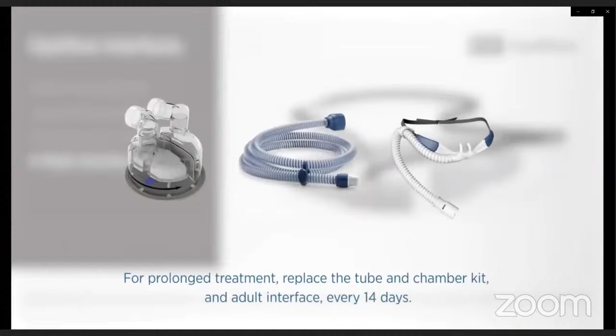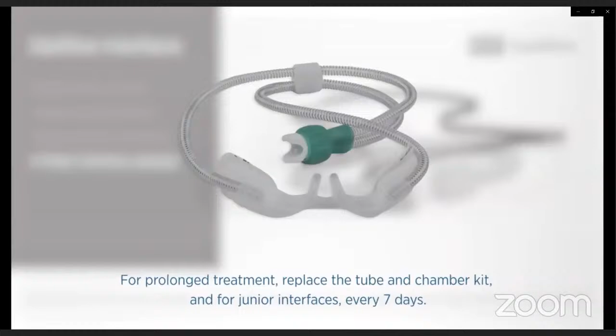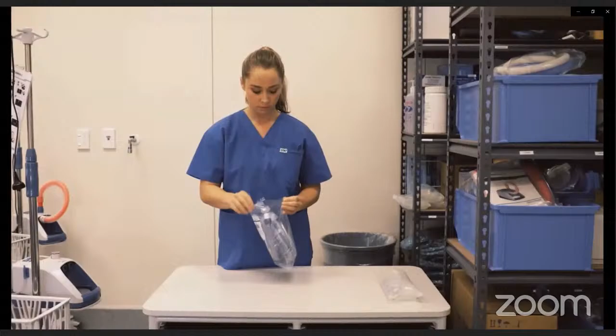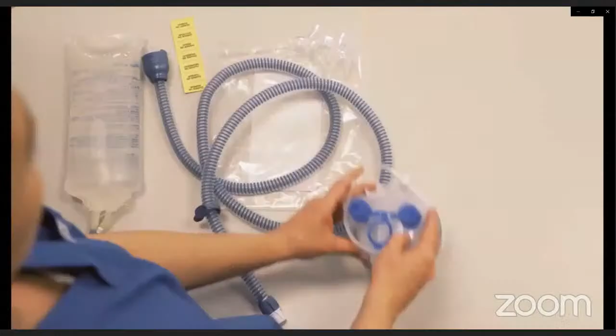For prolonged treatment, replace the tube and chamber kit and adult interface every 14 days, and junior interfaces every 7 days. Open the packaging of the tube and chamber kit. Remove the blue port caps from the chamber by pulling the tear tab upwards, then remove the bracket holding the water supply tube. Fit the supplied adapter over the two vertical ports on the chamber and push on fully. Then clip the water supply tube into position.